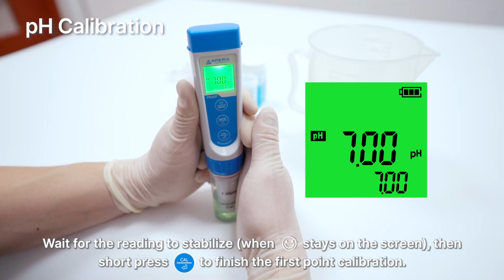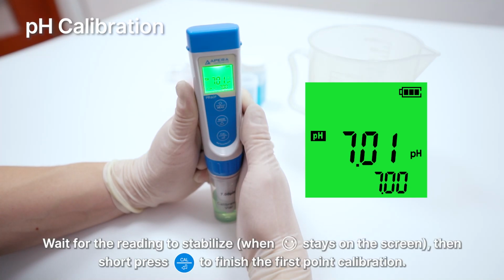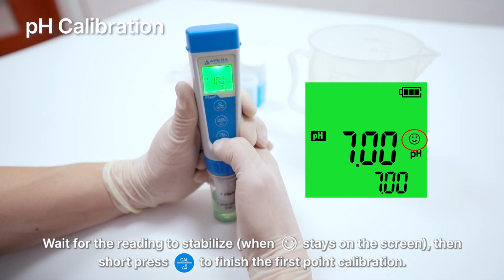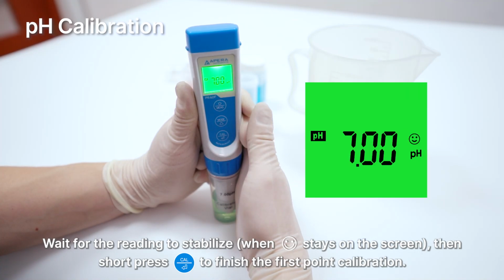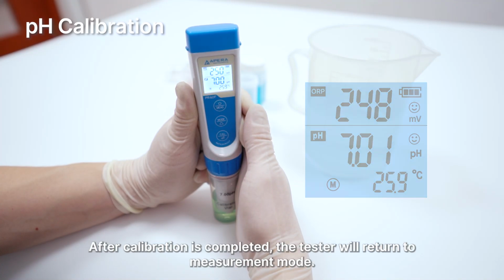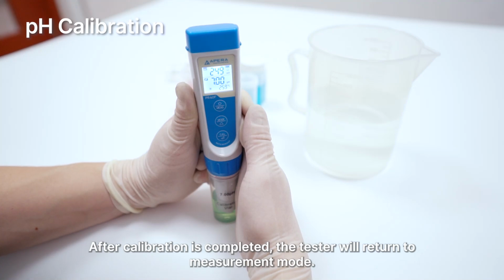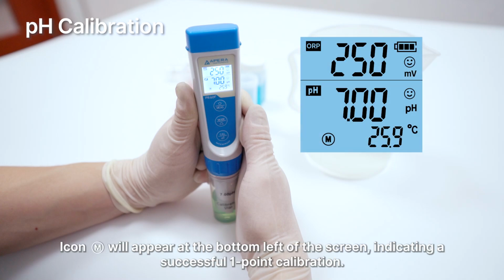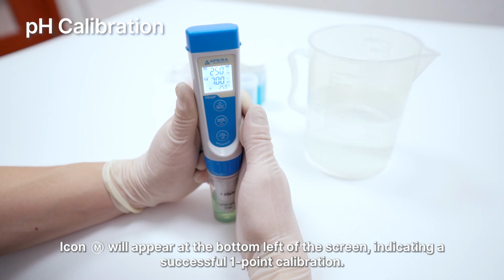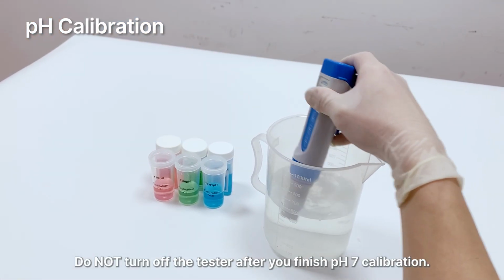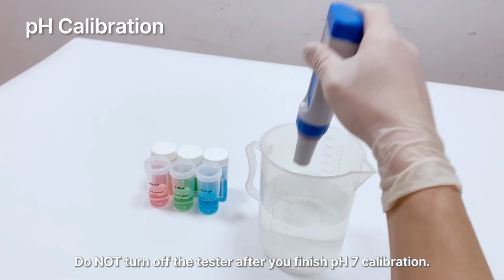Wait for the reading to stabilize, when smile face stays on the screen. Then short press Cal button to finish the first point calibration. After calibration is completed, the tester will return to measurement mode. Icon M will appear at the bottom left of the screen, indicating a successful one-point calibration. Do not turn off the tester after you finish pH 7 calibration.